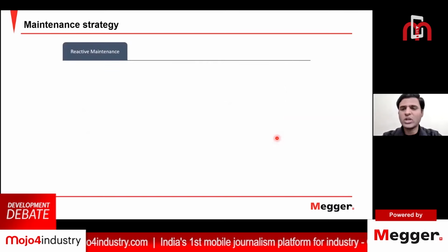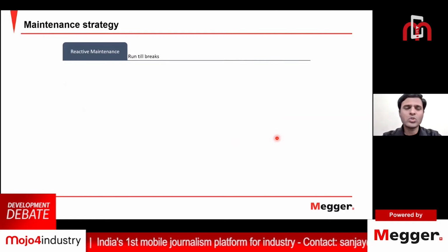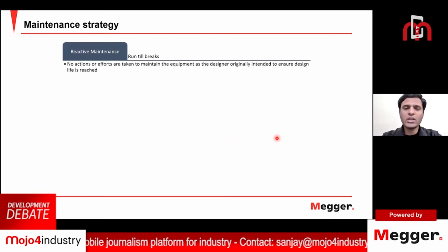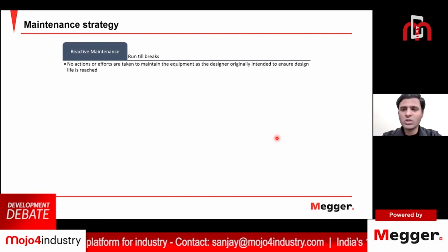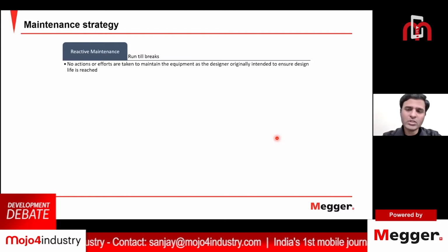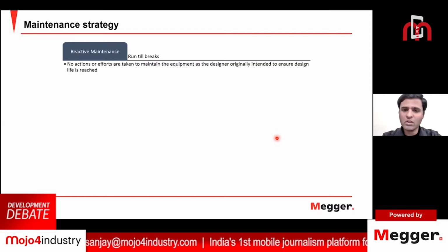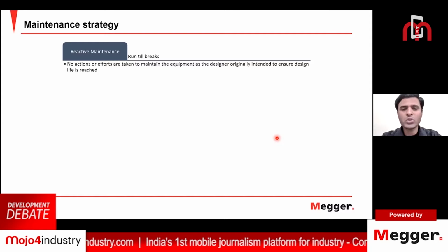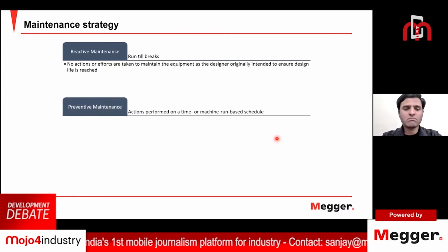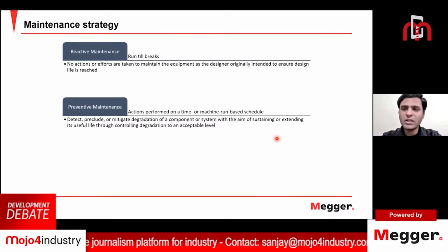There are different maintenance strategies followed by the industry. Conventionally, we used to have reactive maintenance. That means whenever an electrical asset fails, we carry out the maintenance work to identify the faults which may have caused the failure, rectify them, and put the asset back into service. However, industry has well accepted the concept of preventive maintenance. That means maintenance actions based on a periodic or machine-run-based schedule, to detect the degradation of the electrical asset and take the needful actions so that the asset can be used for its designed life cycle and in a reliable manner.